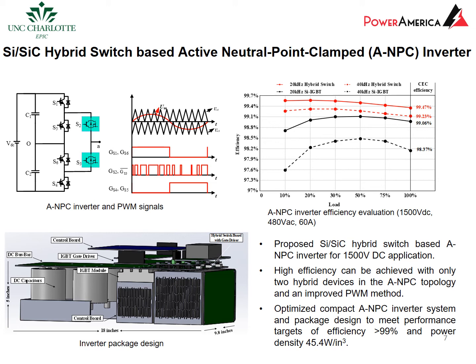With the improved PWM modulation method shown here, only the 2 hybrid switches are switching at high frequency, the switching frequency, while all other switches are switching at twice the line frequency. This way, we were able to reduce the number of hybrid devices in this A-NPC topology while maintaining a very high CEC efficiency, as shown in the efficiency curve.